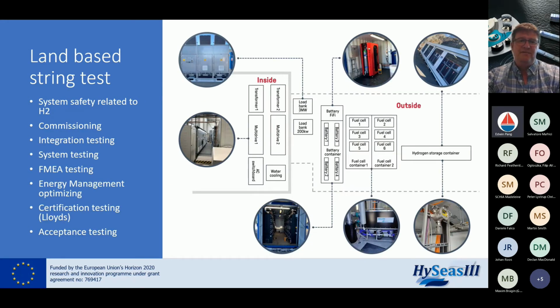Looking at the full string test and the site: outside we have a hydrogen storage container delivered from Linde, and then two fuel cell containers containing three fuel cells each, delivered from Ballard. Then we had a battery container containing four battery strings, two to each side of the switchboard, and a firefighting system for the battery as well. We also had two load banks, one replicating the load from the azimuth thruster and one for the tunnel thruster, which enabled us to complete testing of the rest of the system without actually having the thrusters.